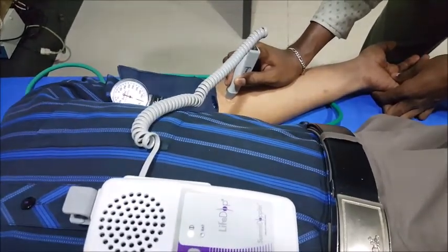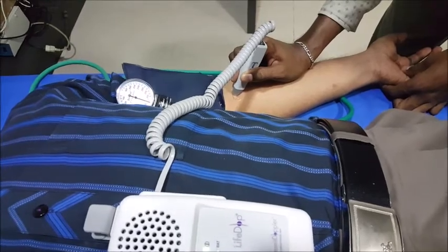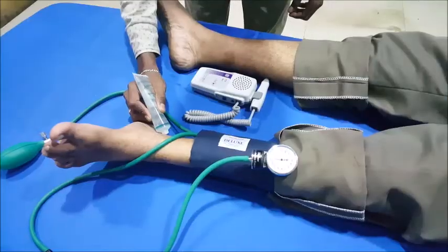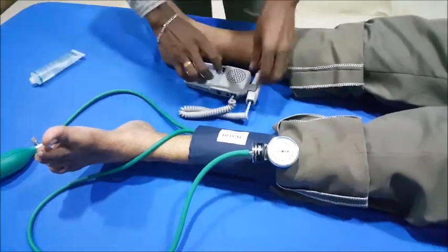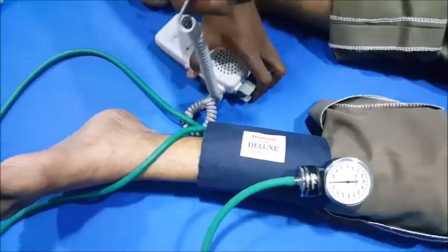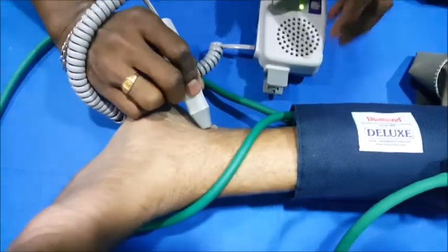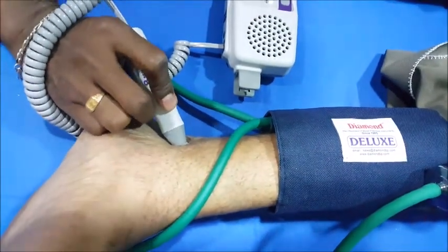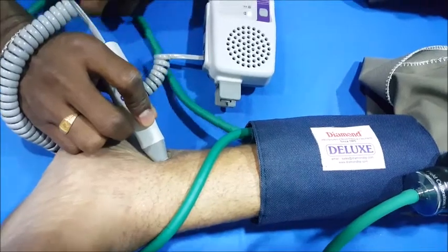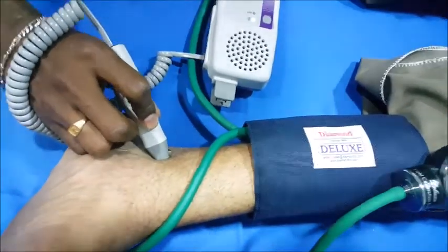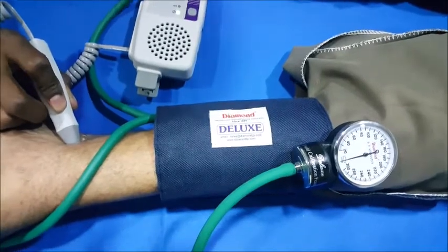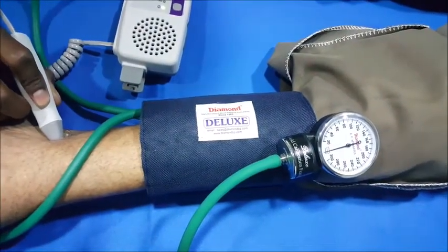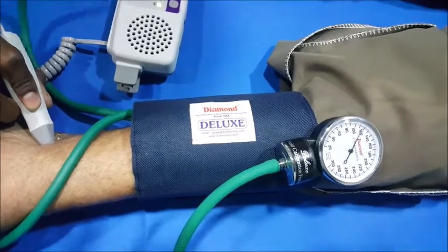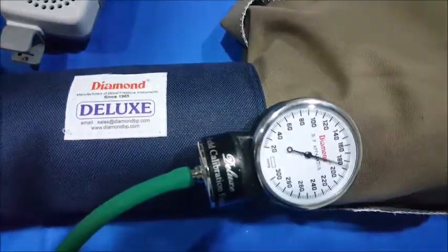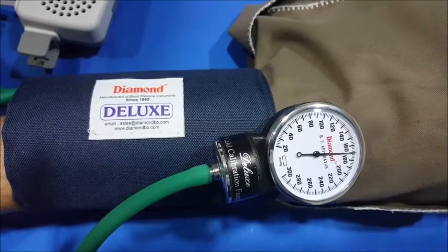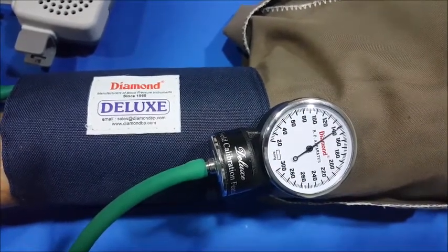Okay. Once you get the pulsatile arterial pressure, then inflate and take the pressure, and then move the position to the posterior tibial area. Keep the probe, see the location just below the bone, adjust the probe angle, you get good sound. Once you get good sound, then without changing the probe, inflate the cuff, stop when the sound stops, then slowly deflate. When the first sound reappears, that's the left posterior tibial systolic pressure.